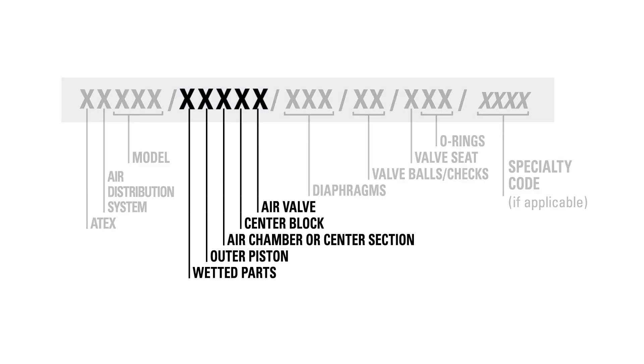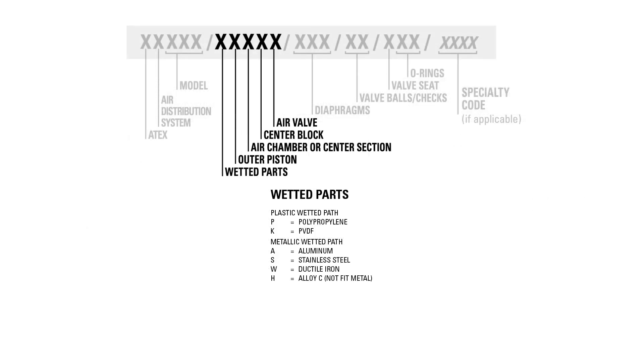The second section identifies the pump's external components, including the wetted parts, outer piston, air chamber or center section, center block, and air valve. The first digit in this section outlines the material of construction for the wetted parts of the pump, which consists of the outer chambers and the manifolds. Wilden offers various plastic and metal material options depending on the application requirements.